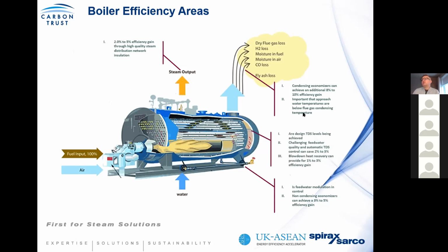Again, we talked about TDS designs. So we talk about the feed water quality. In other words, are you using the right grade of water? We should be looking to achieve a 2 to 3% efficiency gain by improving the quality of water. If, for example, you have high alkalinity or high silica in your soft water, it may make sense to use reverse osmosis grade water, because in doing so, you could significantly reduce your need for TDS blowdown. Again, you can look at heat recovery, and if you put in heat recovery, you can get anywhere from a 1 to 3% efficiency gain.